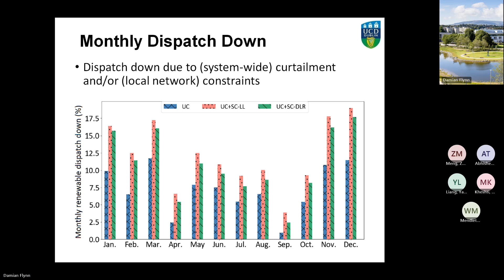You can also convert this into the impact of adding dynamic line rating. The unit commitment is just saying, let's dispatch the system and not worry about the network. The orange and green lines are saying we do need to recognize the network and the impact of dynamic line rating, so you can see the curtailment increasing. We're talking about numbers in double figures, so curtailment is high given the very high renewable penetration.